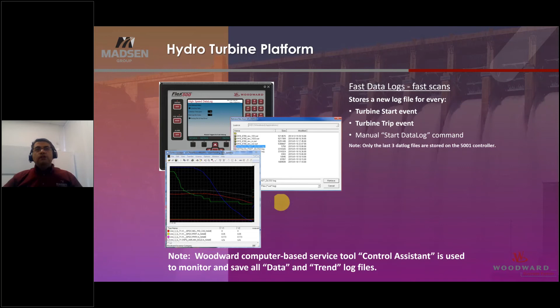Also, if a trip condition happens within the unit, it has the capability to store data from 2 or 3 minutes before the event and 3 or 7 minutes after, depending on how the unit is configured. You can define this time so you're able to test it and know what happened to your turbine during the trip condition. These are all features available in the new 5001.